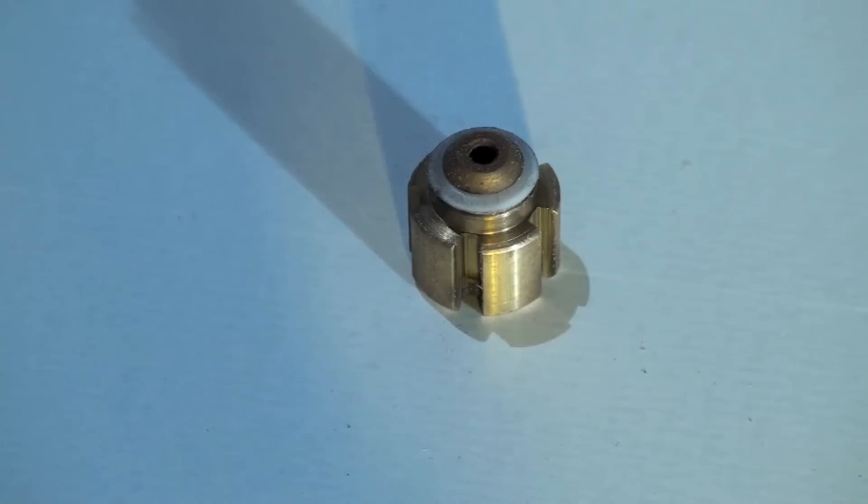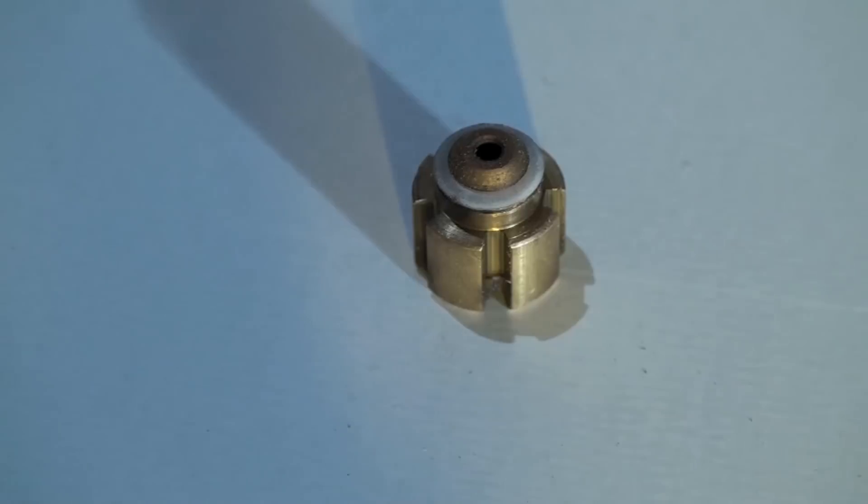A little more about these things. Notice there's a gasket there. The way the body of this thing is designed is this slides back and forth whichever way the refrigerant's going. This is so it can be used in a heat pump.